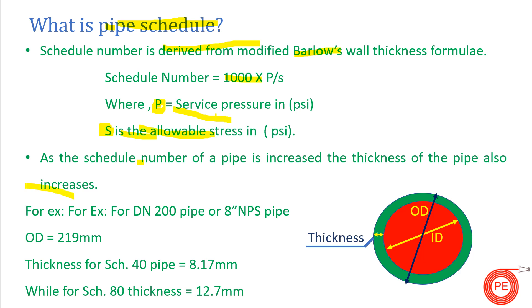As the schedule number of a pipe increases, its thickness increases. For example, for an 8-inch pipe, schedule 40 thickness is 8.17 mm while schedule 80 thickness is 12.7 mm. A separate video covers how to calculate pipe thickness and schedule number in detail. This video focuses on the importance and meaning of schedule number.